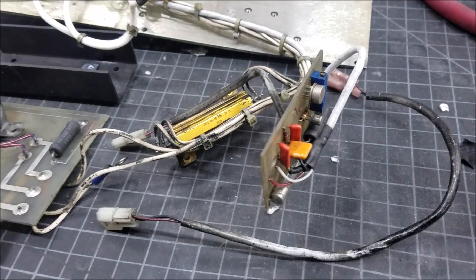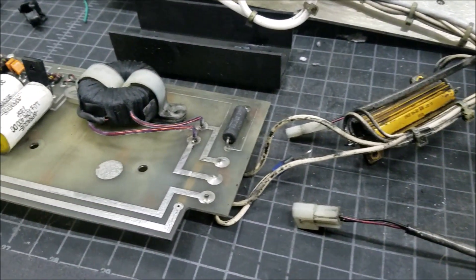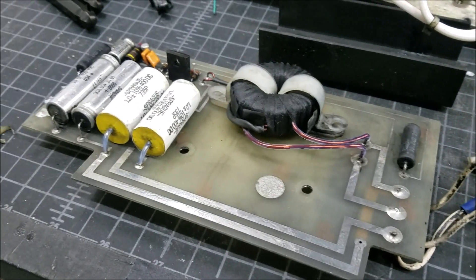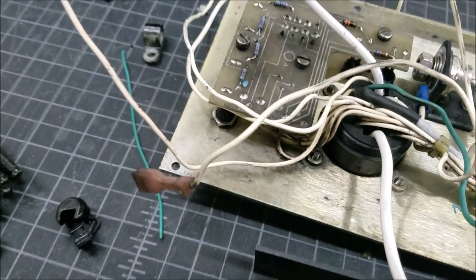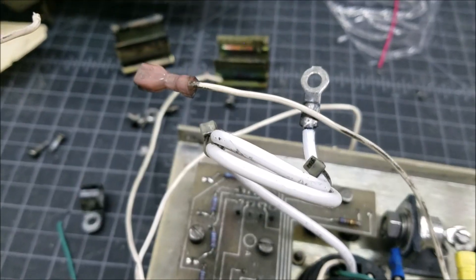The laser head has three circuit boards inside. The smallest one connects to the light sensor, another board with high voltage capacitors and transformer for igniting the laser, and finally the laser power supply input and interface mounted on the side panel.